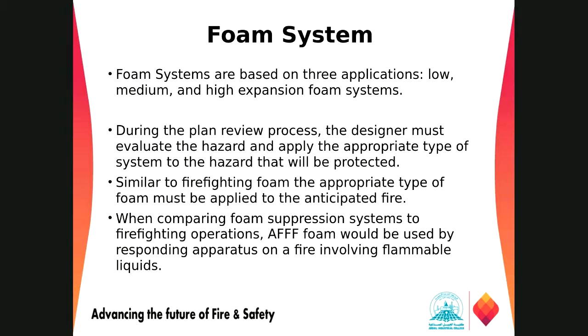So we are moving on to the next one, which is the foam system. Normally, foam systems are based on three applications. We have the low, medium, and high expansion foam. We discussed the foam system in fire protection design and fire protection too, right? So look for those applications. During the plan review process, the designer must evaluate the hazard and apply the appropriate type of system to the protected hazard areas, right? The type of foam must be applied to the anticipated fire. So what is the type of fire, based on that is the requirement of the flow.